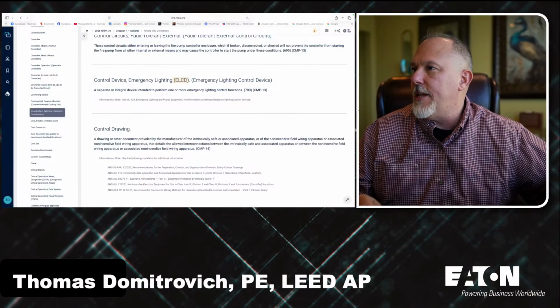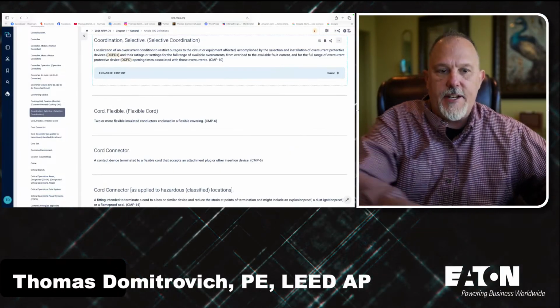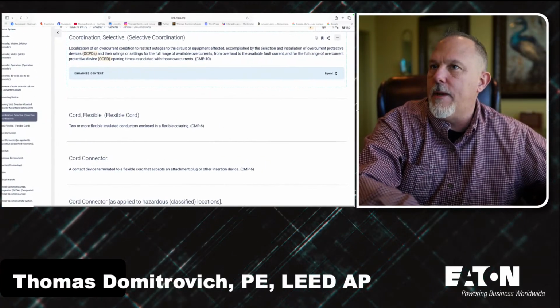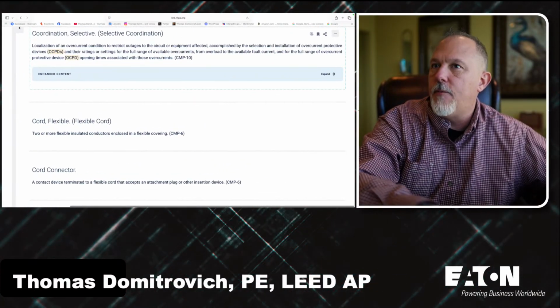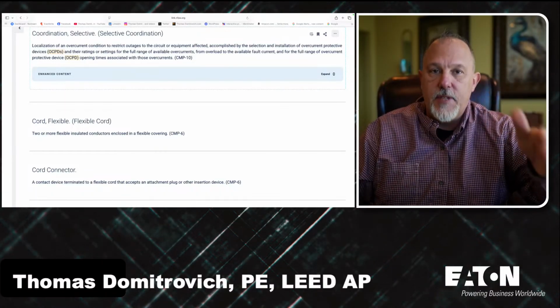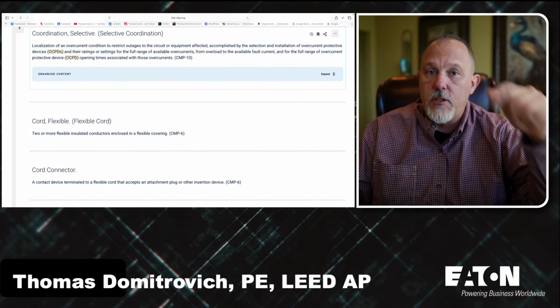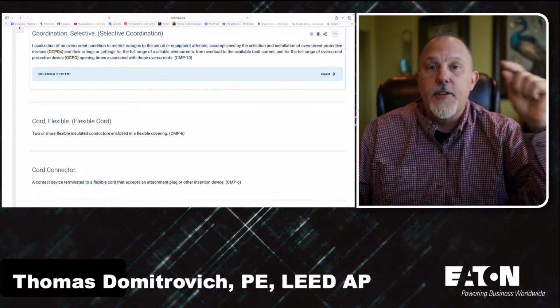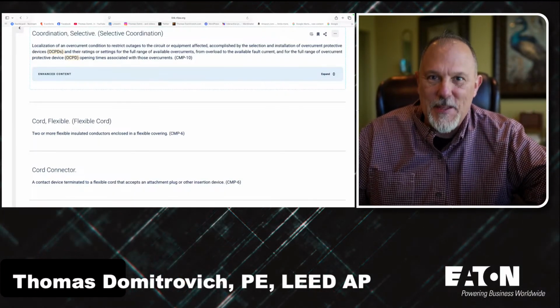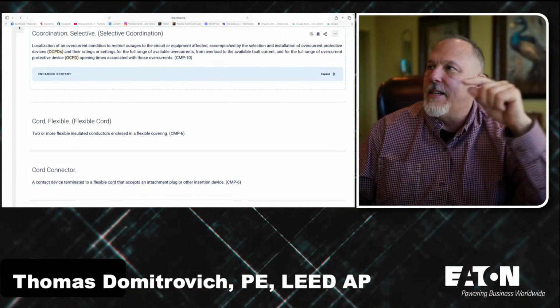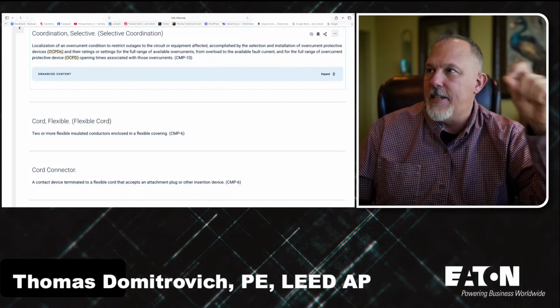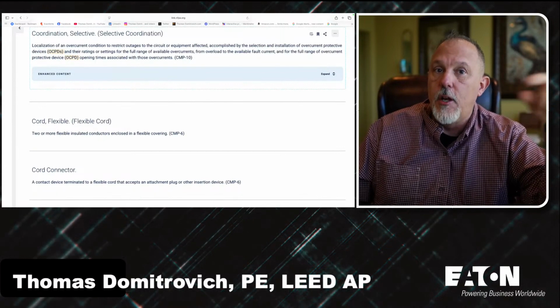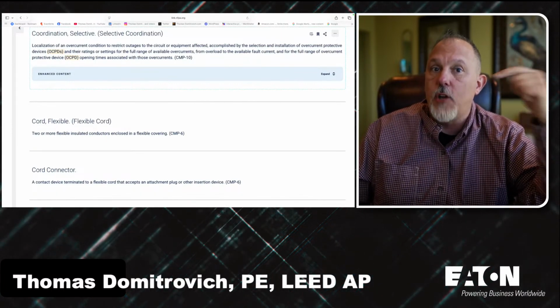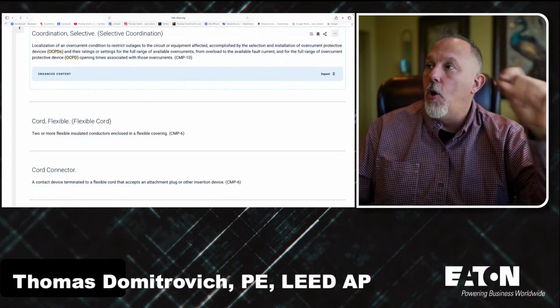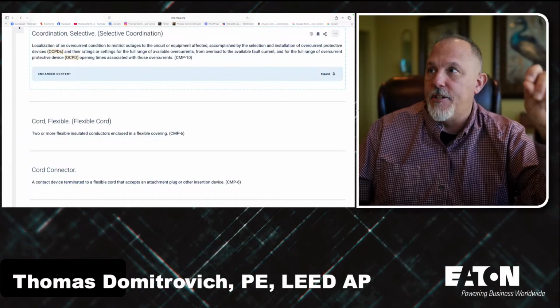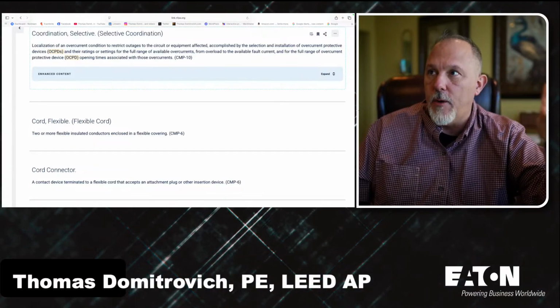So, coordination, selective. This is the definition. Take a look at what it says, and remember what the concept is. The concept is that the circuit breaker closest to the fault is the one that clears. So it says localization of an overcurrent condition. Remember, overcurrents can be short circuits, ground faults, overloads, all of that. Overcurrent condition to restrict outages to the circuit or equipment affected.